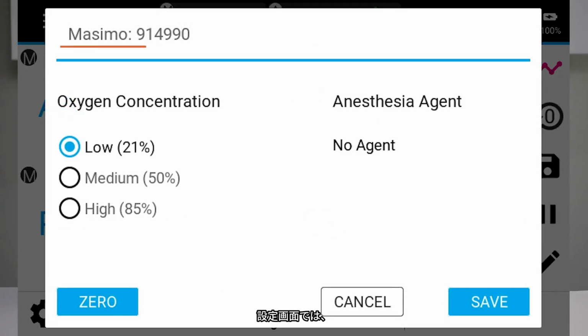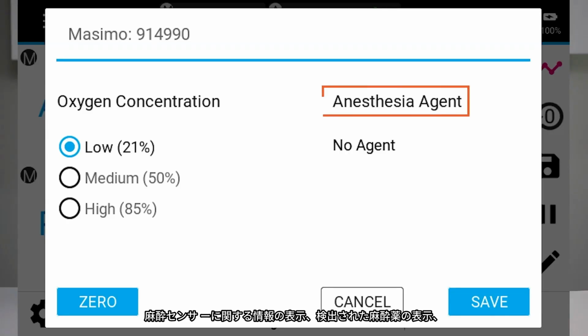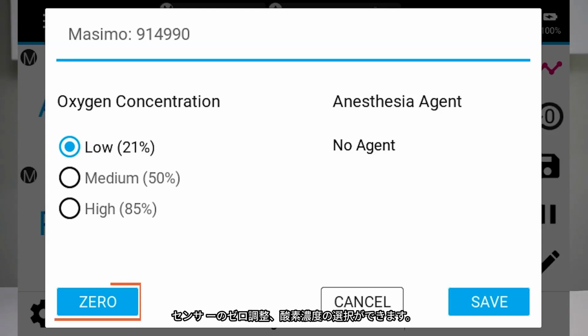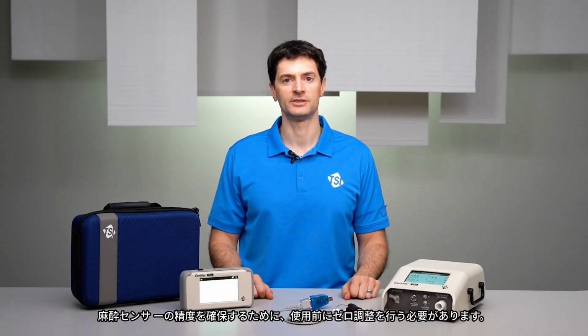In the settings screen, you can view information about the anesthesia sensor, view the detected anesthetic agent, zero the sensor, and select the oxygen concentration. 3 different oxygen concentration levels can be selected to match the oxygen percentage that's present in the gas delivered from the device under test. The anesthesia sensor should be zeroed before use to ensure its accuracy.